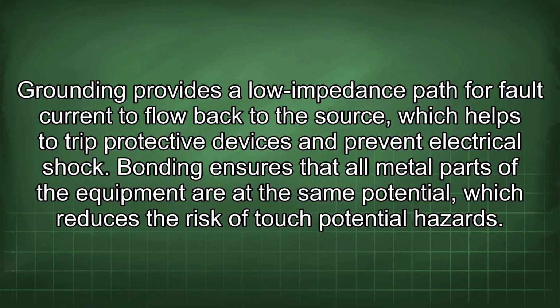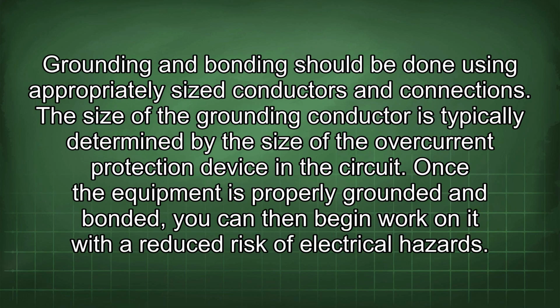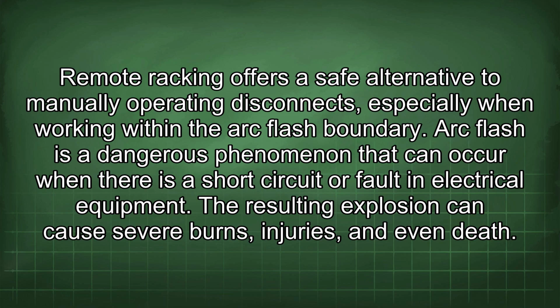Bonding ensures that all metal parts of the equipment are at the same potential, which reduces the risk of touch potential hazard. Grounding and bonding should be done using appropriately sized conductors and connections. The size of the grounding conductor is typically determined by the size of the overcurrent protection device in the circuit. Once the equipment is properly grounded and bonded, you can then begin work on it with a reduced risk of electrical hazards. Remote racking offers a safe alternative to manually operating disconnects, especially when working within the arc flash boundary.